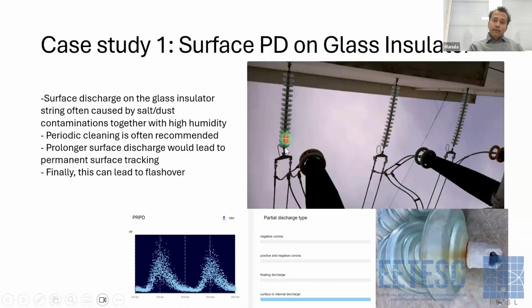When we keep this unattended, or when we don't take any remedial action, over a long time it might go to the surface tracking level. As you can see from the big picture at the bottom, this is the glass insulator string that has been removed from the location, and you can clearly see surface tracking was initiated there, so that there is a carbonized path that has been initiated.